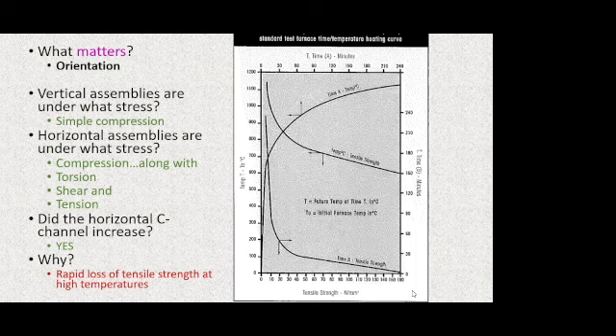You know, at the branch line level, it's a 1-inch pipe with some water in it. Why are we using all thread rod with cracked concrete anchors and clevis clamps closely spaced together? Is that way overkill or what? To hold that up in the air. The cold water pipe right next to it, the hot water pipe right next to it, not being supported like that. And the reason is that at 2000 degrees, when that sprinkler system still needs to be there, and that standpipe still needs to be working for those 2 hours, that's what the residual tensile strength is of the steel support system.